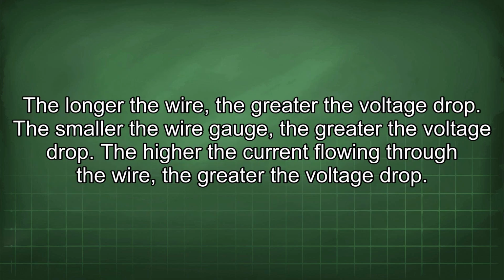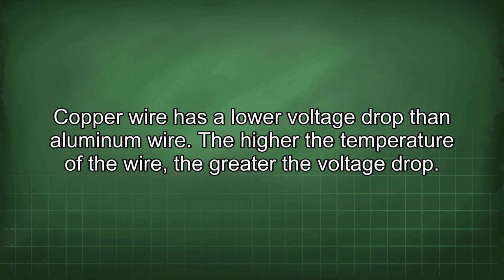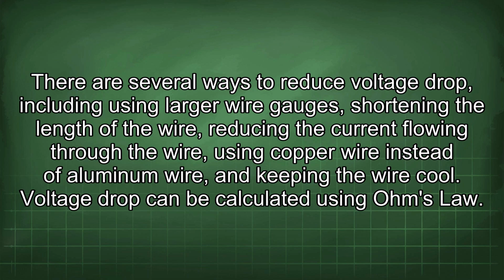The longer the wire, the greater the voltage drop. The smaller the wire gauge, the greater the voltage drop. The higher the current flowing through the wire, the greater the voltage drop. Copper wire has a lower voltage drop than aluminum wire. The higher the temperature of the wire, the greater the voltage drop. There are several ways to reduce voltage drop, including using larger wire gauges, shortening the length of the wire, reducing the current flowing through the wire, using copper wire instead of aluminum wire, and keeping the wire cool.